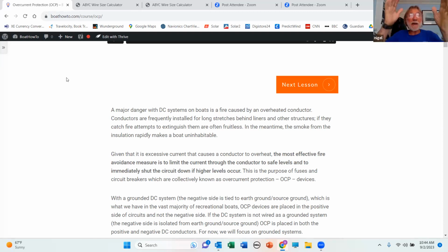If you're looking at a panel where you've got an incoming feeder conductor from the battery, and then you've got all these circuit breakers attached to a bus bar in the panel, and then you've got conductors coming out of the circuit breakers. Those circuit breakers are actually physically attached to the bus bar, so it's 0 inches, because they're protecting the circuits downstream of them. But if it's not that kind of a situation, then the generic rule is 7 inches.